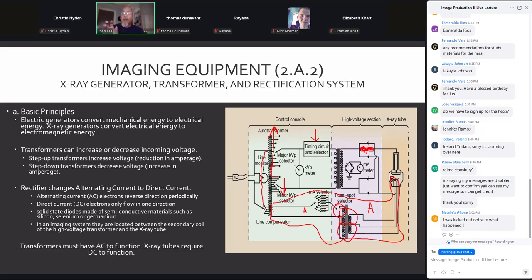We want to be operating in volts. You want to make sure that the controls that we touch are in volts and not in kilovolts. So the control panel is always operating around volts and amperes. It's when we use this high tension transformer, a few coils on this side, the primary side, lots of coils on the secondary side, we get a great increase, tens of thousands fold increase in voltage. That's where we get kilovoltage. Now, because our voltage is now in kilovoltage by going through that transformer, the opposite is going to happen to our current. So in this circuit, current goes from amperage down thousands of times to milliamperage. And again, milliamperage is what is measured from cathode to anode in our X-ray tube.